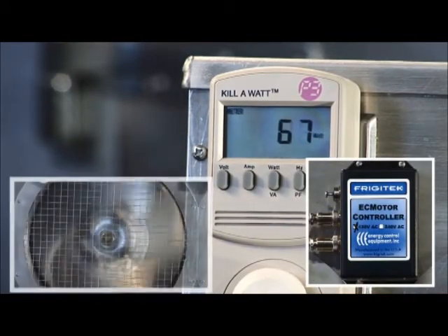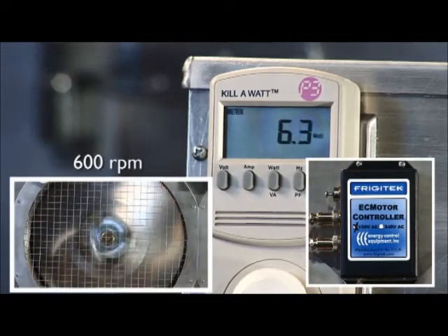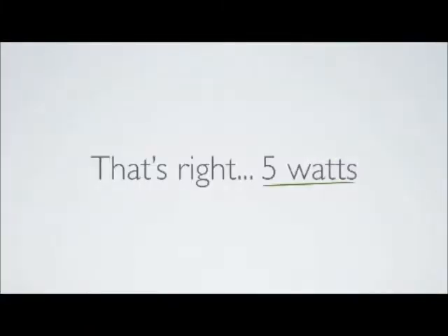Now we will simulate the compressor off-cycle. The Frigitek controller will slow the EC fan motor to 600 RPM, and it is now only consuming about 5 watts of electricity. That's right — 5 watts, when before it was consuming close to 150 watts 24/7.